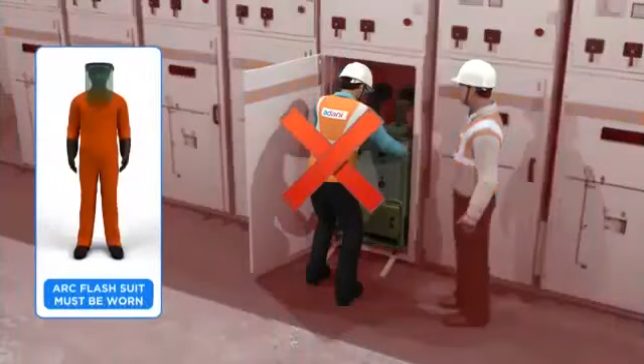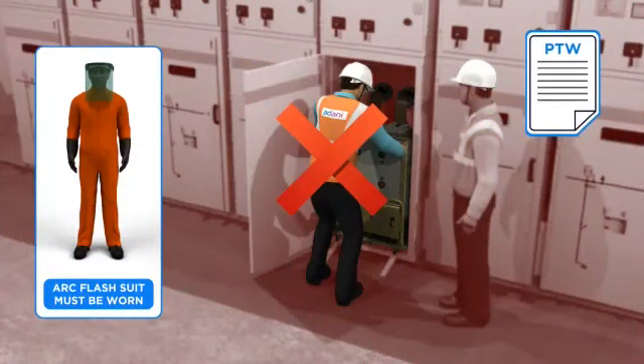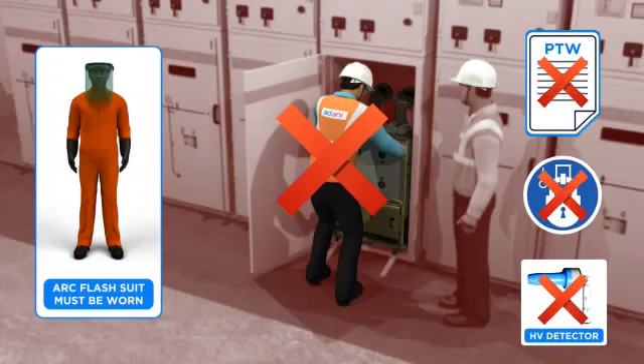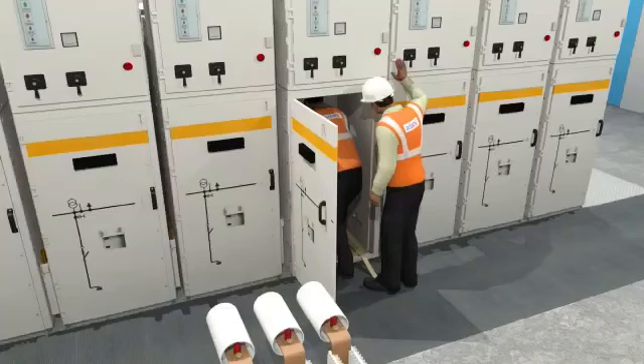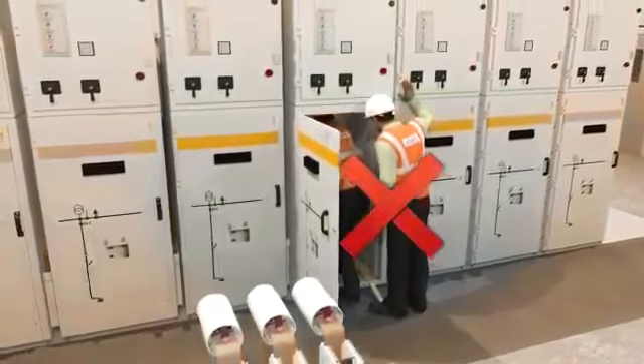What went wrong? The technician unnecessarily opened the live bus bar shutter using shortcuts. The arc flash suit was not worn, though available on site. The existing procedure on PTW and LOTO was not followed. The HV detector was not used to check the absence of voltage. Safe distance and correct positioning were not maintained while working on the panel.